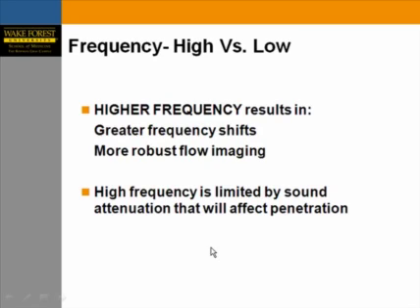Regarding frequency — high or low — you need to understand the advantages of each. Higher frequency results in greater frequency shifts and more robust flow imaging. However, you can't always use higher frequency because sound attenuation limits penetration.